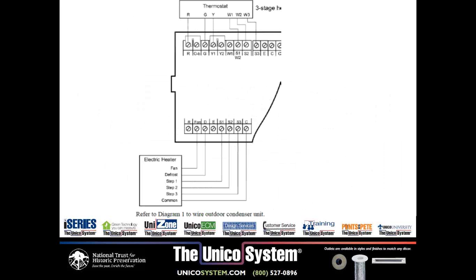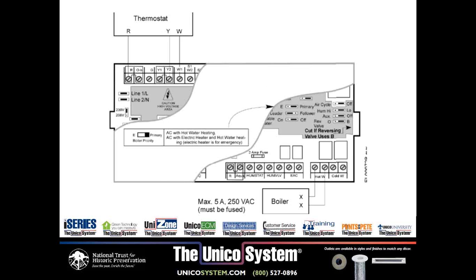Now here you can see we can have up to 3 stages of heat with our hot water or our electric heater. This is true with the larger heaters that are out there. They have increments of 5 kW that would come on as the outside temperatures change. Then you would energize step 1, step 2, and then finally step 3.